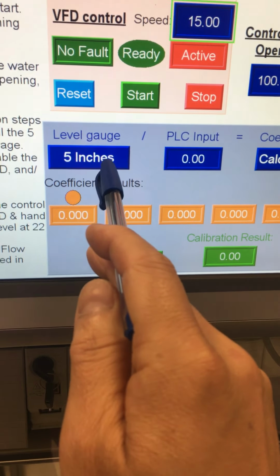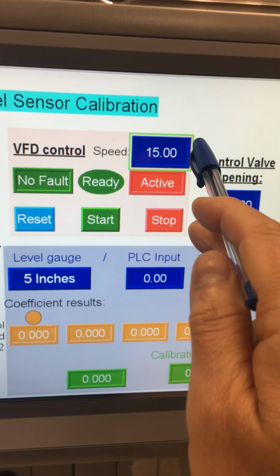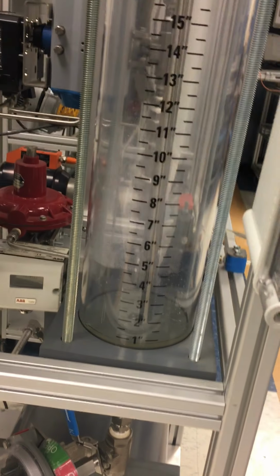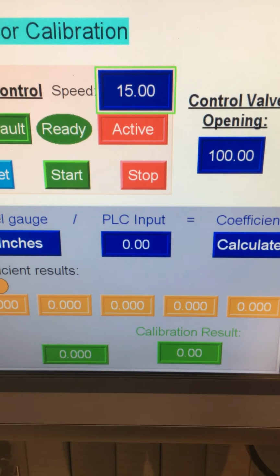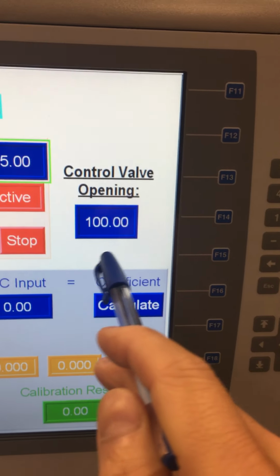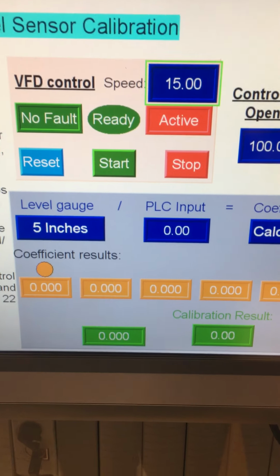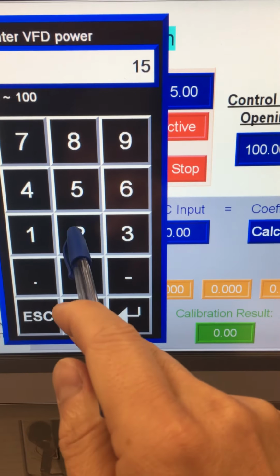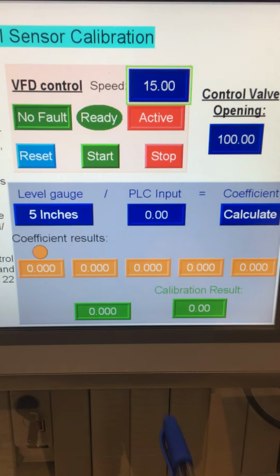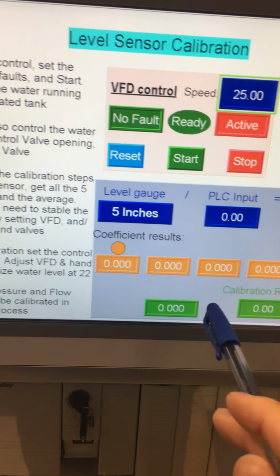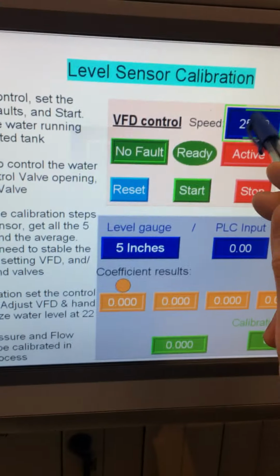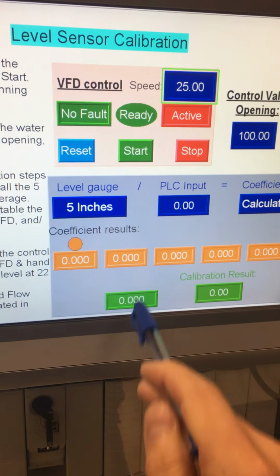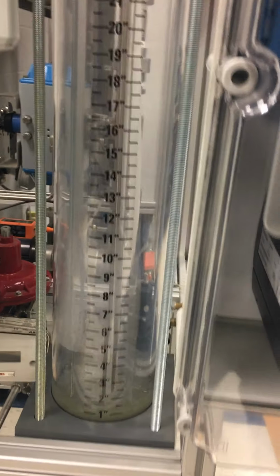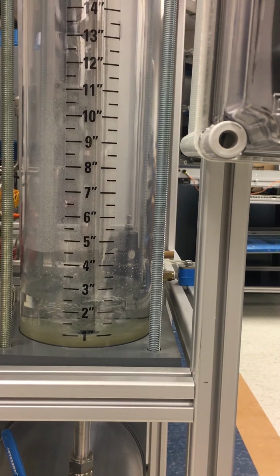That's what we should set up as a target, because right now the VFD is running at very low speed, so you can see the water cannot accumulate inside there. We should set up a fairly high percentage. You can also control the valve and play with it, but in order to shorten this video, I don't want to do that part again. So we can just increase the speed maybe to 25% on the VFD, and we should see something change, but not a lot, not high enough. Let's go to 45%. Now we can see some action on the tank. We need to keep an eye on the level. Right now it's at 2 inches.